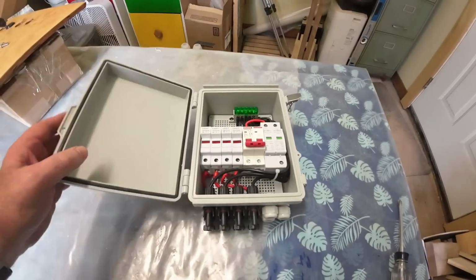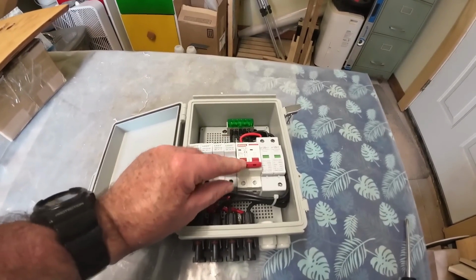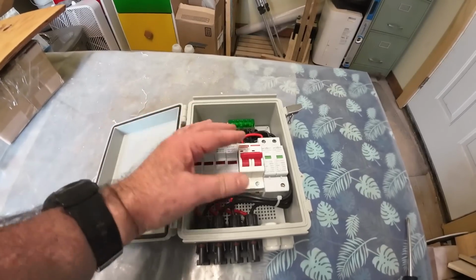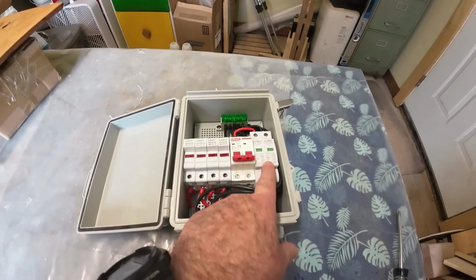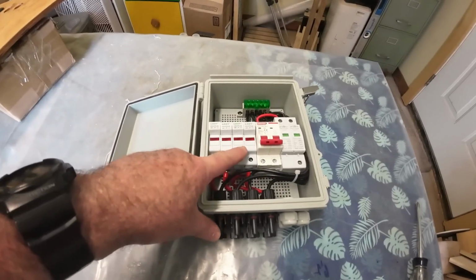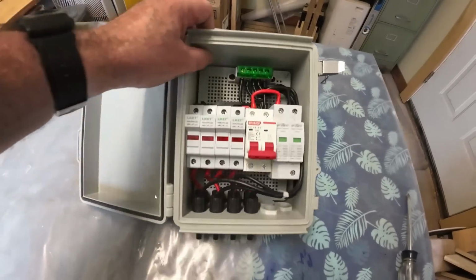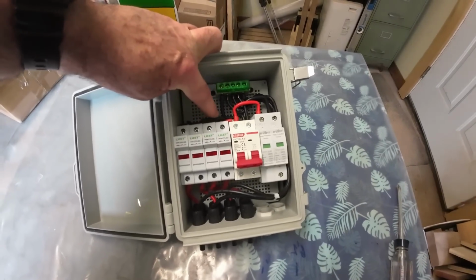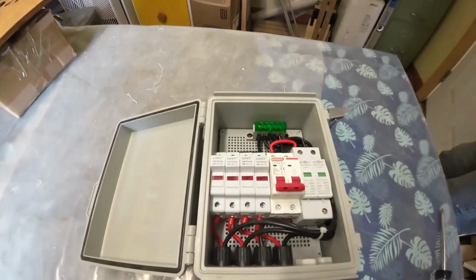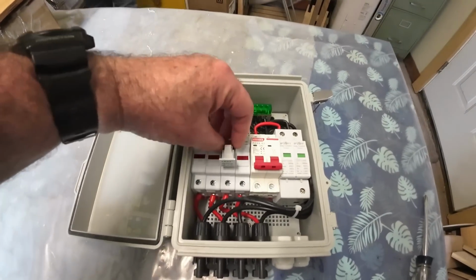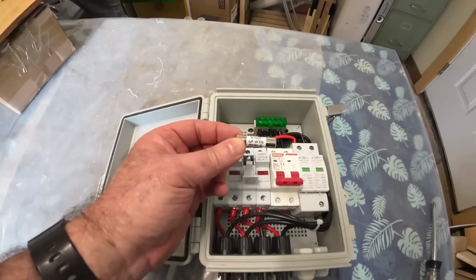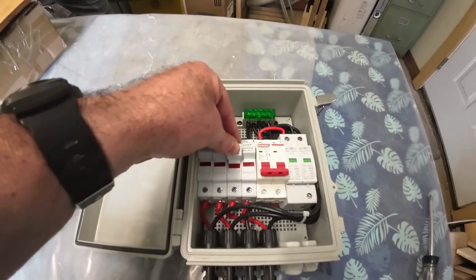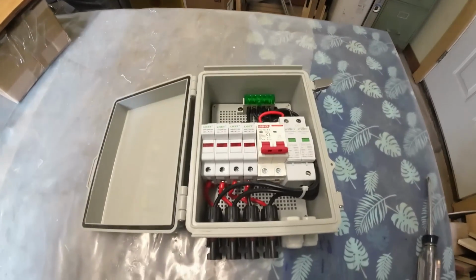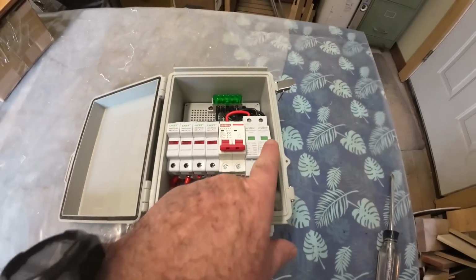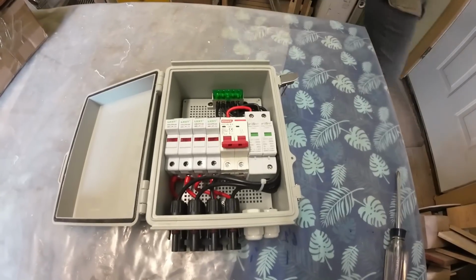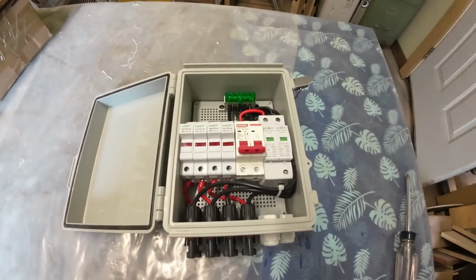The nice thing about the solar isolator panel is we can use this circuit breaker to turn the solar panels on and off. It also has surge protection, and each of these inlets is for combining, so all the commons are combined and across the top all the positives are combined. Each has a 15 amp fuse, making it fusible, so if there's an overload it'll protect the electronics. Same for the surge protector - if there's a lightning strike, hopefully it'll protect all the electronics attached throughout the system.